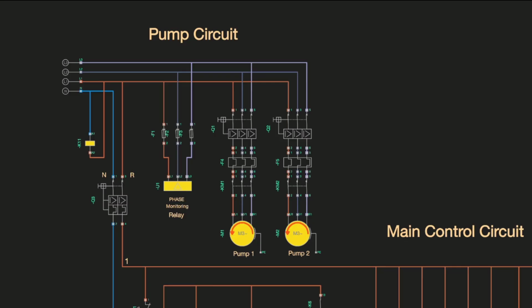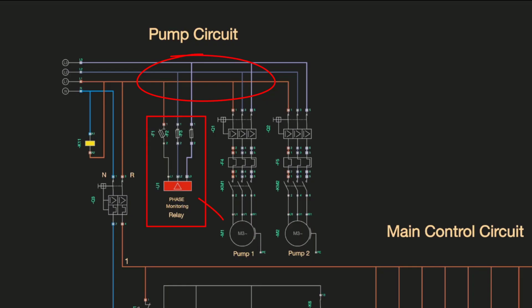That's where the phase monitoring relay comes in. It constantly compares all three phases, and the moment the difference exceeds the set imbalance threshold, like 5% or 10%, it reacts instantly by cutting off the supply. So instead of letting the motor slowly destroy itself, the relay sacrifices operation to protect the equipment.